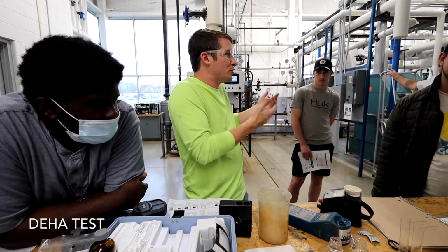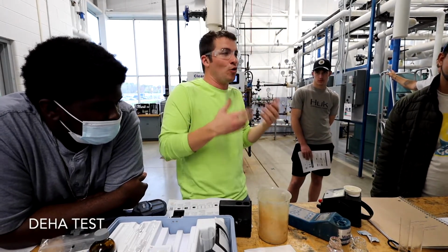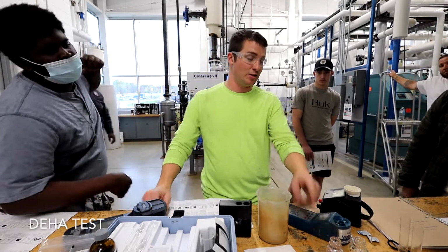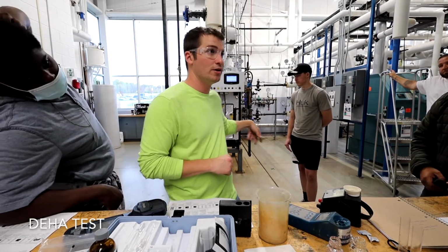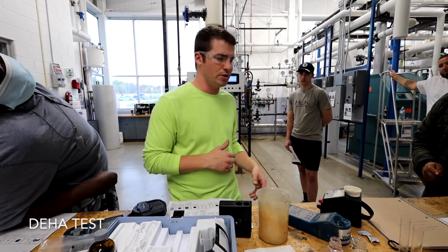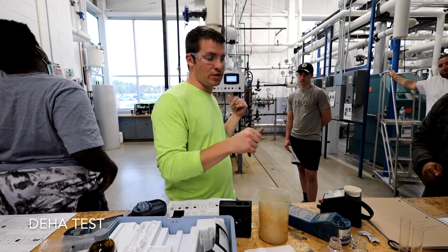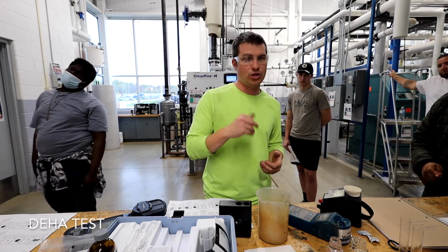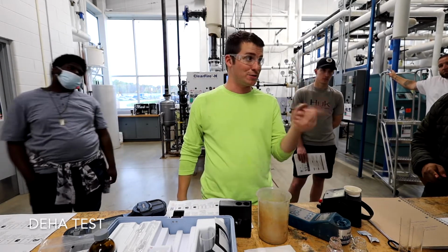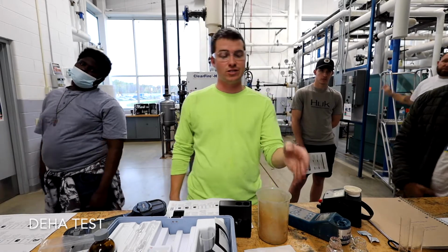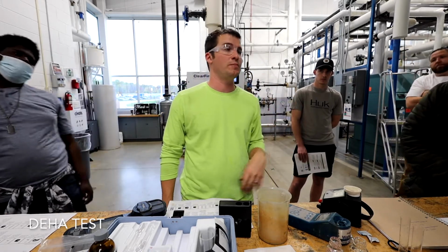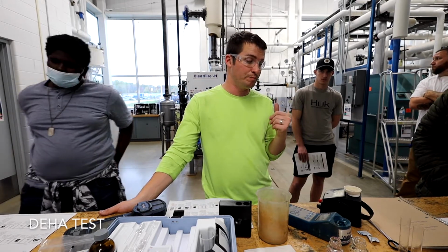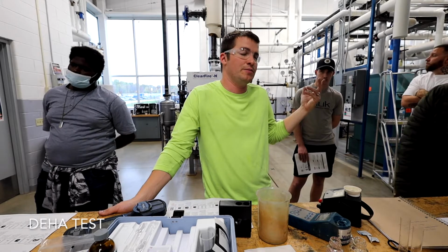Again, this boiler does not run the way a normal boiler really will run. So we're going to find that today, the only way to get this up really is either to purposely dump a boatload of water out of your boiler down the drain, which I wouldn't necessarily recommend, or just manually run that pump in hand. I can show you how to do that on that controller, and it'll run for 10 minutes and then shut back off to artificially boost it. That's probably what you're going to have to do. So you'll come in and do your test. If it's low, you're going to turn that pump on and run it for 10 minutes in hand and boost that level up. That's kind of how we're going to have to handle that, because you don't really have any demand for that boiler.